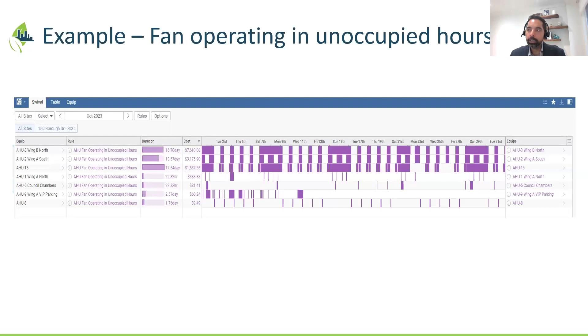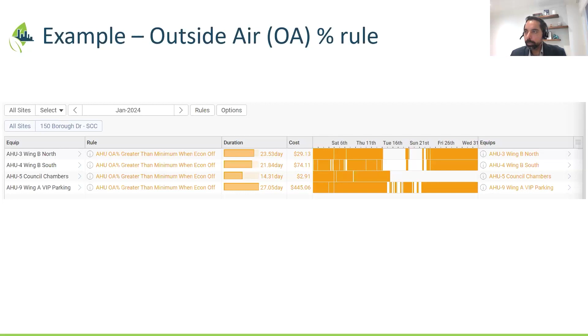Another rule, on outside air, tells you how much outside air you're bringing in above the ASHRAE 62.1 requirements when the system isn't running an economizer. It's related to your heating thermal load. When you do the benchmark component analysis originally with the building and see a high heating thermal load, this is probably one reason why: you're bringing too much outside air into the building. This rule tells you exactly how much you're spending, daily or cumulatively, by bringing in too much outside air when it's not needed.